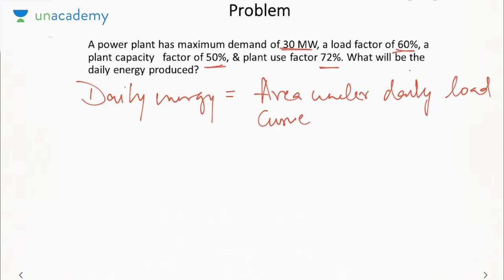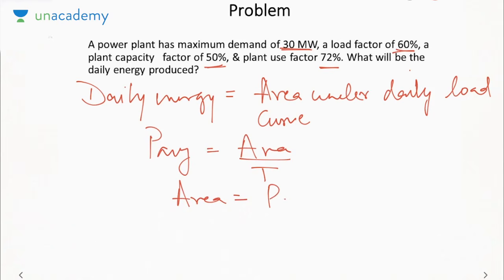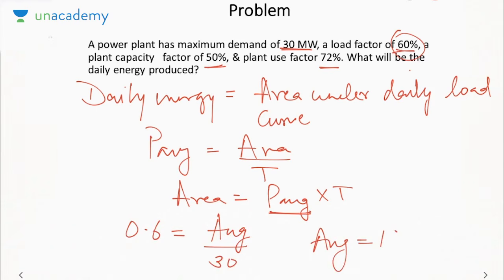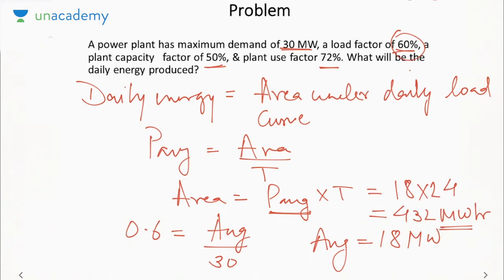Okay, so if it is asking the area under the daily load curve, we know average demand is equal to area by time. So area can be determined as average demand multiplied by time. So for that we need average demand. Time will be 24 hours. Now maximum demand is given and load factor. So load factor is 0.6, average by maximum is 30. So average will be 18 megawatt. Now area will be equal to 18 into 24, which is equal to 432 megawatt hour. So this much energy is generated daily.